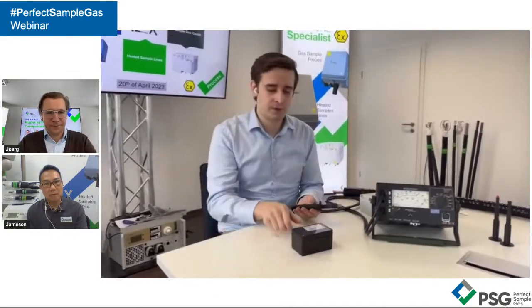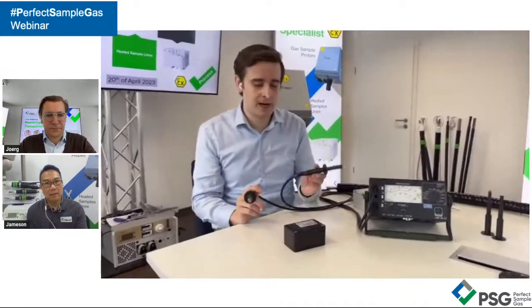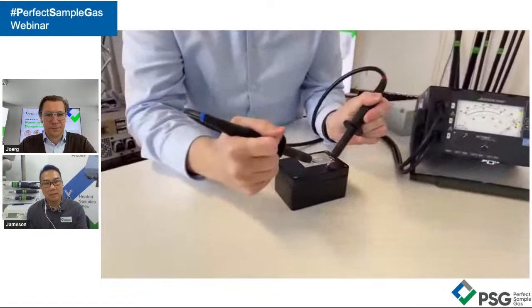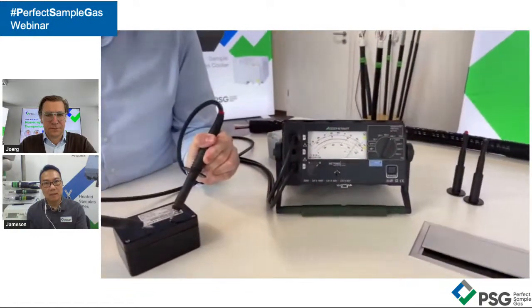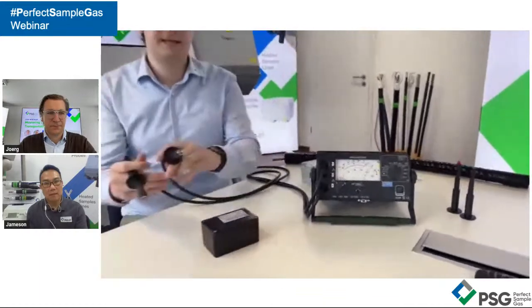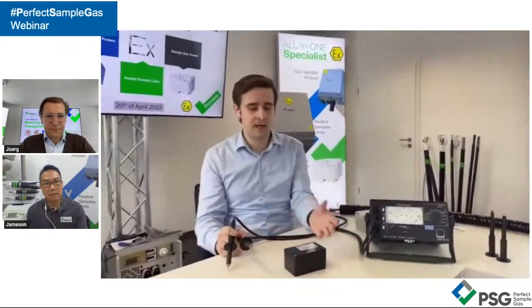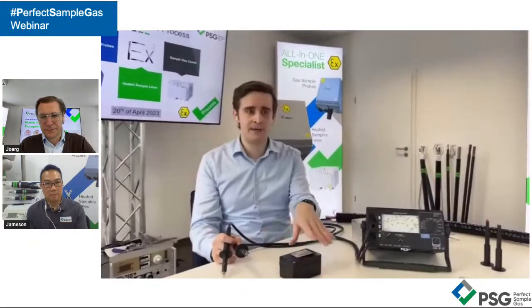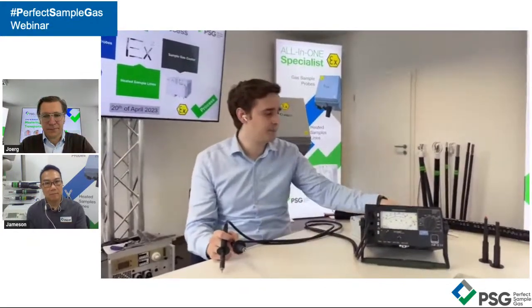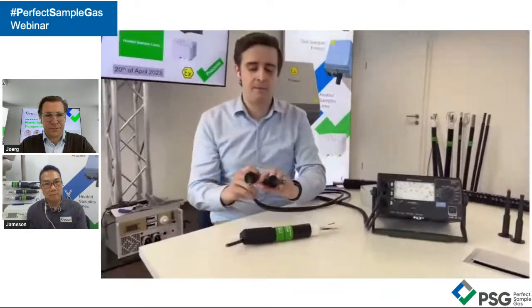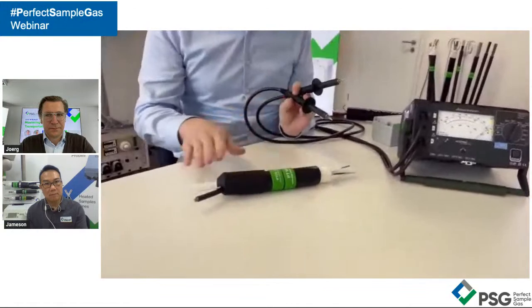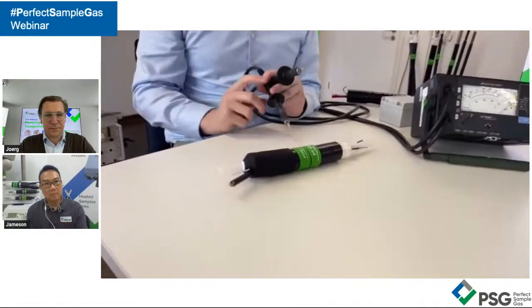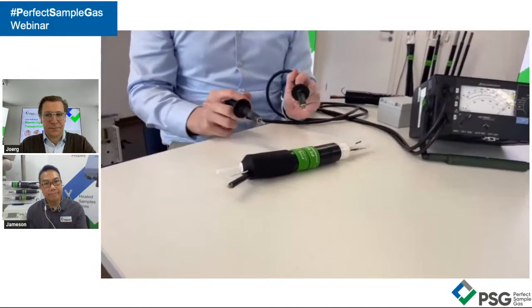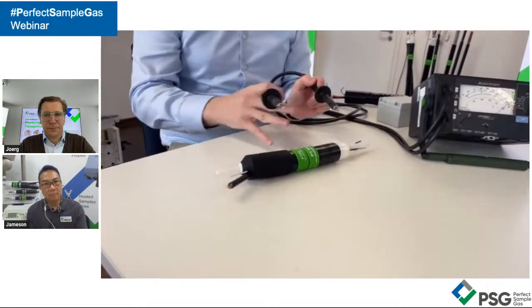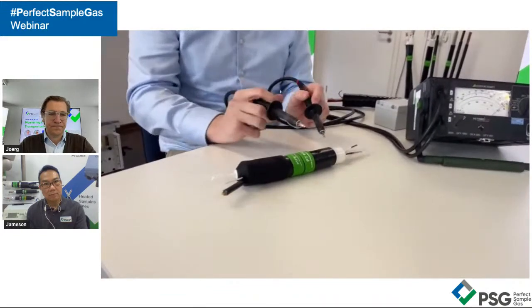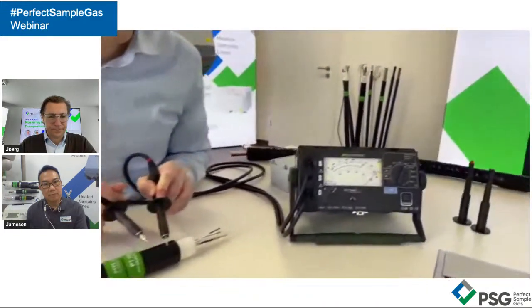Usually you use junction boxes like this one, specially designed for ATEX areas. What this means, could you see here? There is conductivity on the surface. That means that unwanted static electricity can flow to the protective earth and isn't a risk anymore for your ATEX system. But pretty much the same goes for our heated sample lines. What you can see here is one of our usual PVC jacketed heated sample lines. We can also deliver this one with an ATEX heater, but this one would have just regular non-conductivity, as you can see over here.